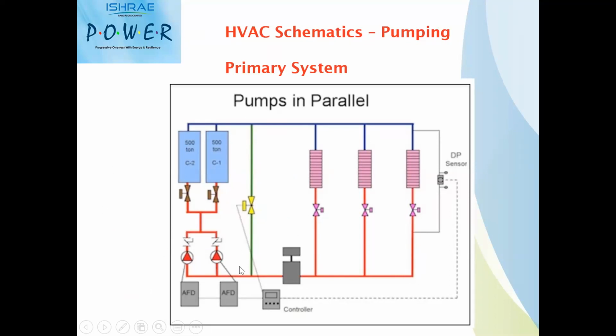So this variable primary system will have, for example, if you have variable load in a particular building, we can have these pumps as a variable primary system as well, which will cater to the load based on the load variation in the system. So this is a very simple schematic where you will have only one set of pumps which will be catering the water to your chiller as well as the load side. So the primary variable system with water-cooled or air-cooled chillers will make it a very simple installation for a typical plant room application.